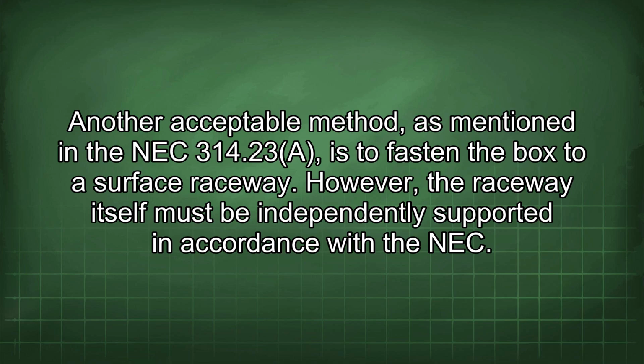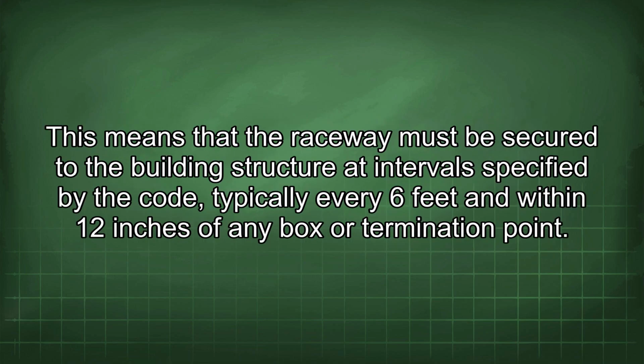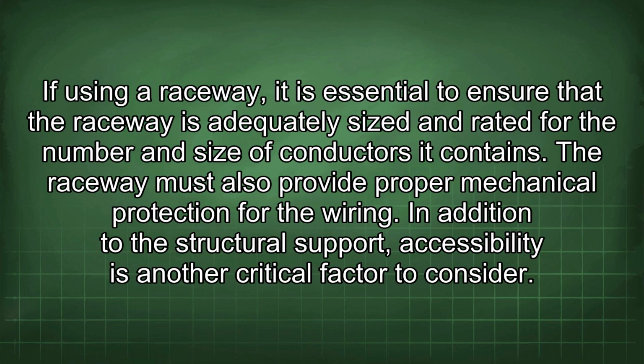Another acceptable method, as mentioned in the NEC 314.23(a), is to fasten the box to a surface raceway. However, the raceway itself must be independently supported in accordance with the NEC. This means that the raceway must be secured to the building structure at intervals specified by the code, typically every 6 feet and within 12 inches of any box or termination point. If using a raceway, it is essential to ensure that the raceway is adequately sized and rated for the number and size of conductors it contains. The raceway must also provide proper mechanical protection for the wiring.